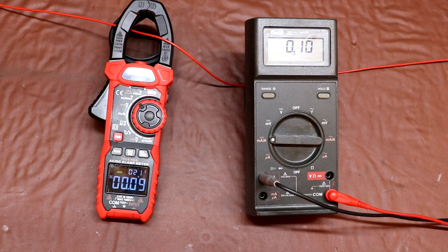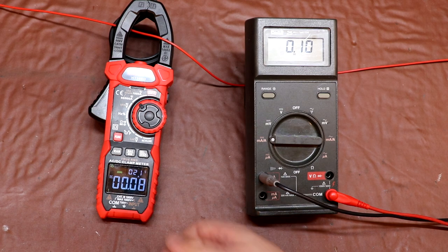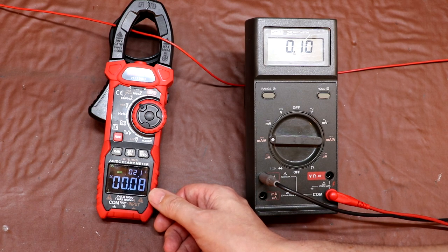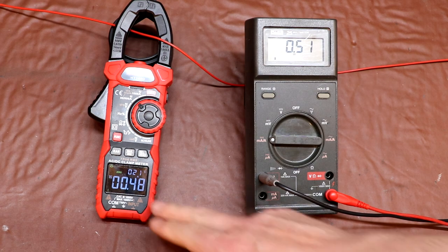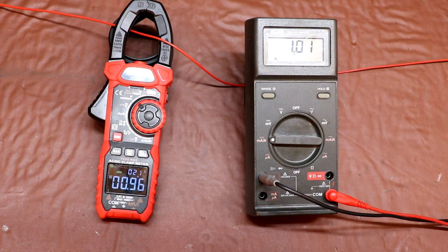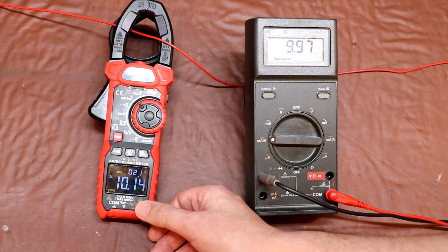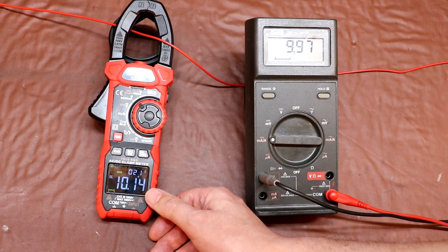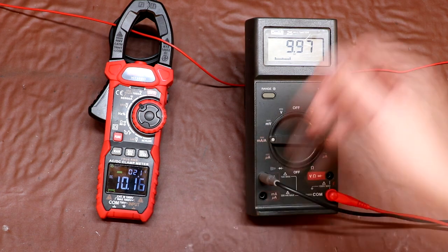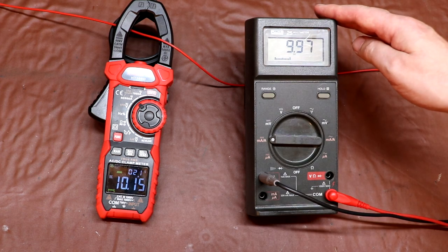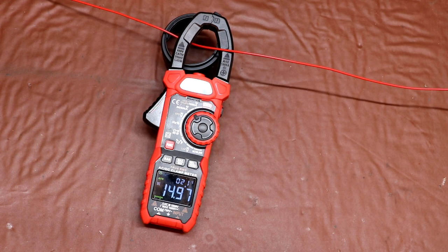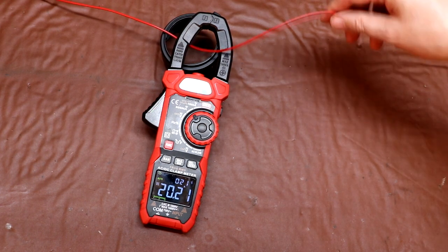So just the same as the AC current measurement range, it appears that the DC measurement range starts working at about 100 milliamps. Below 100 milliamps, our first digit really doesn't appear to do very much. At 500 milliamps, we're just 2 counts out, and at 1 amp, again, we're just a few counts out. At 5 amps, we're spot on. With a set current of 10 amps, we do appear to be about 14 counts out, but in fairness, I also can't be certain of the calibration of my Fluke 25 here. With 15 amps set, the KAIWEETS meter is just 2 counts low, and with 20 amps set, my cables are now starting to smoke.